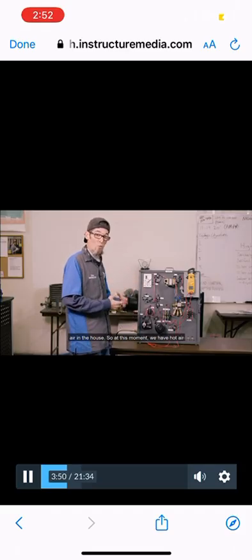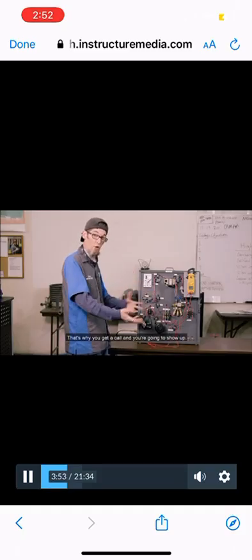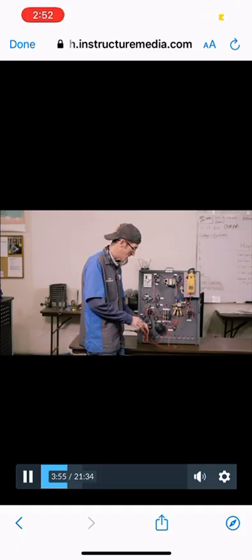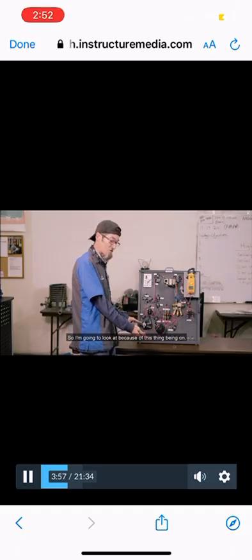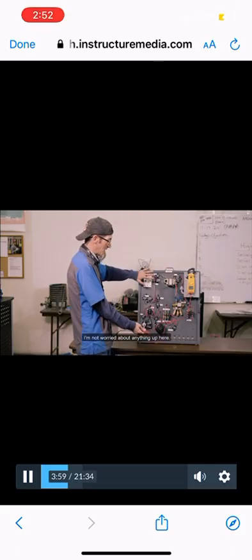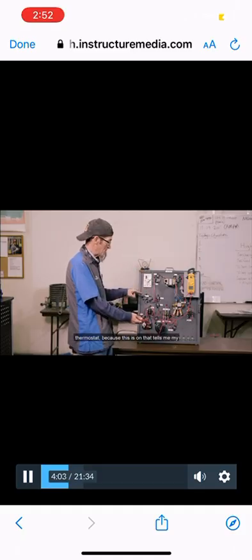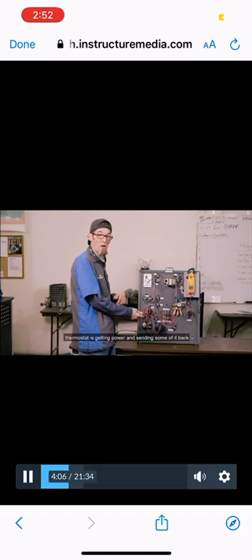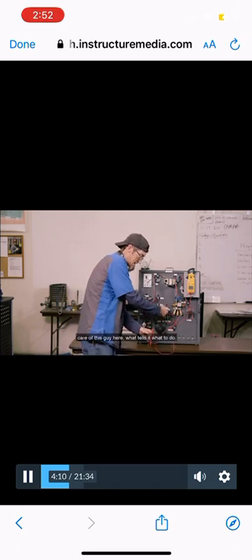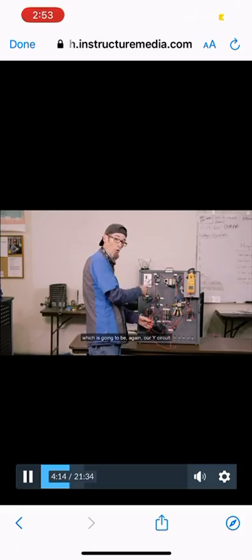So at this moment, we have hot air blowing in the house. That's not good. That's why you get a call and you're going to show up. Because this thing is on, I'm not worried about anything up here: my high voltage, my transformer, not even my thermostat. Because this is on, that tells me my thermostat's getting power and sending some of it back out. So I'm going to look at the circuit that takes care of this guy here, what tells it what to do, which is going to be again our Y circuit.